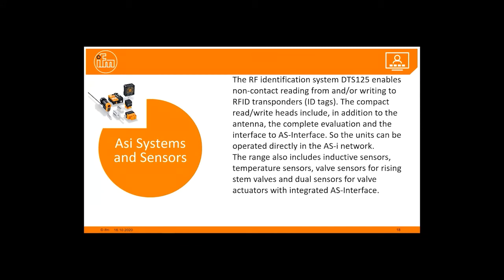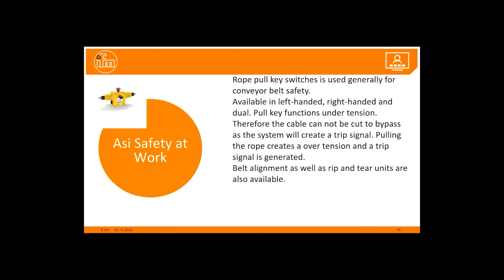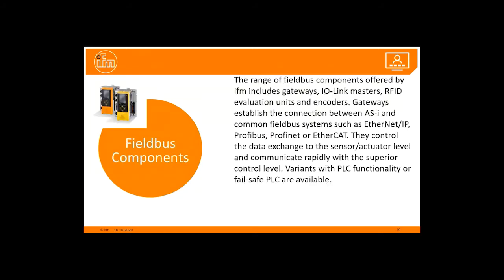Rope pull key switches are used generally for conveyor belts, available in left-handed, right-handed, and in dual. Pull key functions under tension. So what does that mean? Therefore, the cable cannot be cut to bypass, as the system will create a trip. Pulling the rope creates an overtension and it trips as well. So there's no overcoming the safety aspect of the pull key. Belt alignment as well as rip and tear units are also available.